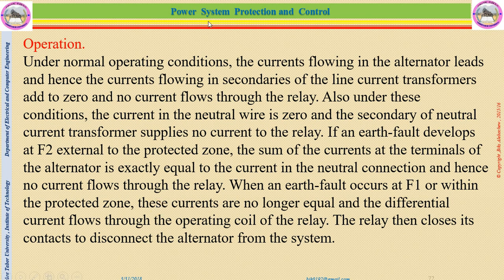Under normal operating conditions, the current flowing in the alternator is balanced, and hence the currents flowing in the secondaries of the line current transformers sum to zero, and no current flows through the relay. Also, under those conditions, the current in the neutral wire is zero, and the secondary of the neutral transformer can supply no current to the relay.